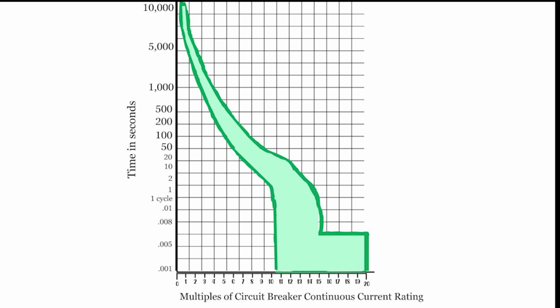If you notice, the graph has two dark green lines that almost mirror each other with a light green shaded area in between. What that means is that at any point on the graph where the conditions are met, the circuit breaker could take that amount of time to actually trip. So if we're looking here around the 20-second mark and 7 times the amperage, according to this graph, which is not accurate, of course, it could take anywhere from 20 to 200 seconds to trip. That's just to give you an idea of how these graphs are set up. Again, I made this graph real quick just to show you guys. So the numbers in the graph are by no means to scale. Keep that in mind.